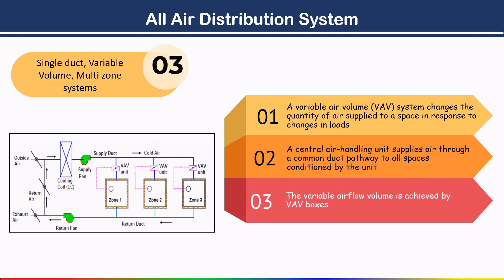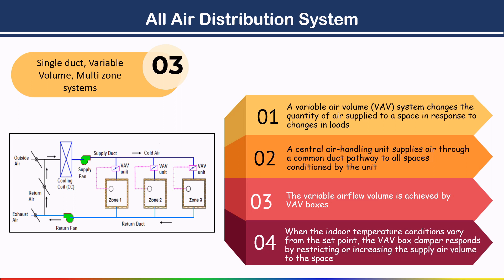Variable air volume is achieved by VAV boxes. When the indoor temperature condition varies from the set point, the VAV box damper responds by restricting or increasing the supply air volume to the space. Each zone is provided with a VAV box — a terminal control box — that adjusts the air supply volume in response to the zone thermostat.